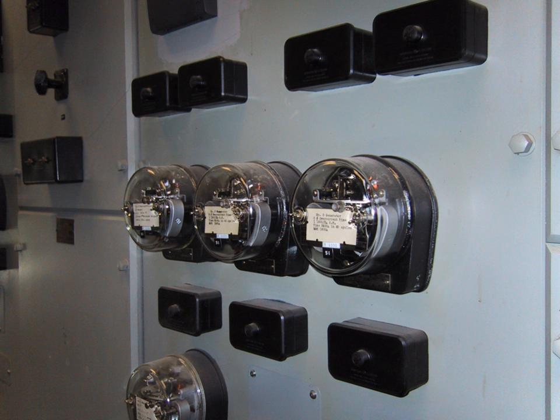The boundary of the protected zone is uniquely defined by the location of the current transformers. Time grading with other protection systems is therefore not required, allowing for tripping without additional delay. Differential protection is therefore suited as fast main protection for all important plant items. Differential protection can be used to provide protection for zones with multiple terminals and can be used to protect lines, generators, motors, transformers, and other electrical plant.